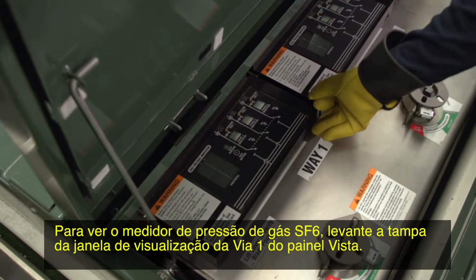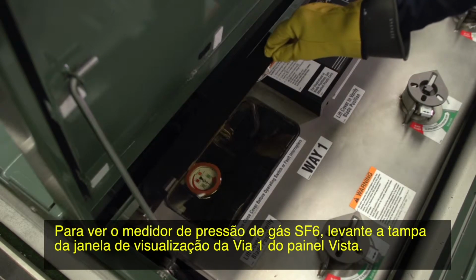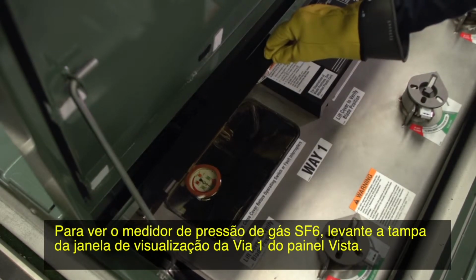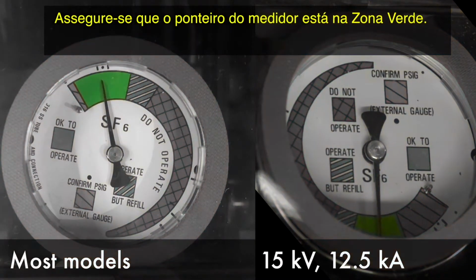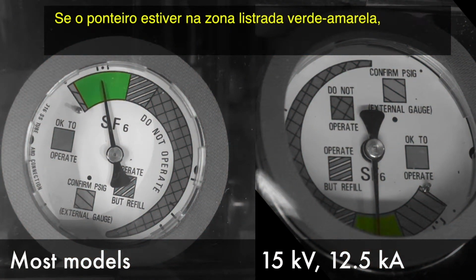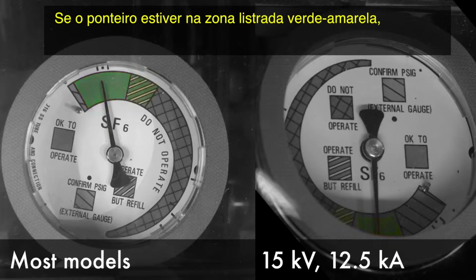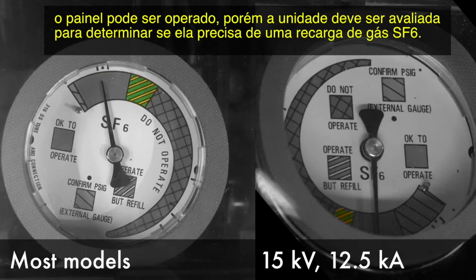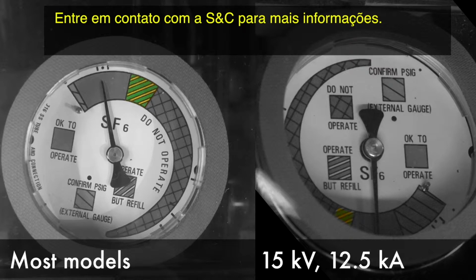To view the SF6 gas pressure gauge, lift the viewing window cover of Way 1 of the Vista switchgear. Ensure that the pressure gauge is in the green zone. If the pressure gauge is in the green and yellow stripe zone, the switchgear can be operated, but the unit must be evaluated to determine whether it needs to be refilled with SF6 gas. Contact S&C for more information.